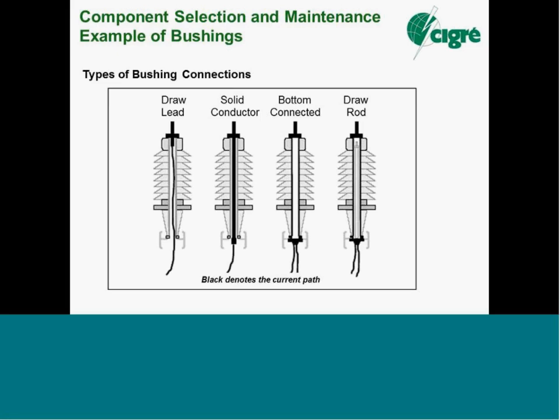So, useful illustrations here. We see the different ways that a condenser bushing could be connected. So you do have to be careful in understanding your condenser bushing. How is the line lead connected into the bushing? How are you to remove the bushing, if first you don't study the manual, the type of bushing fit in the transformer, and read how the bushing should be disconnected if it is removed from the transformer?